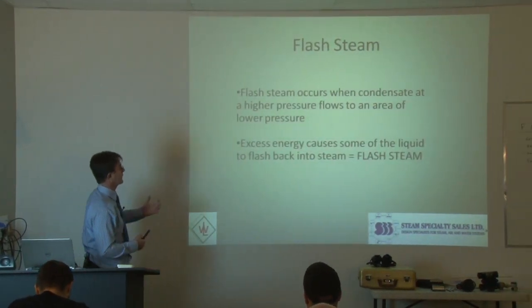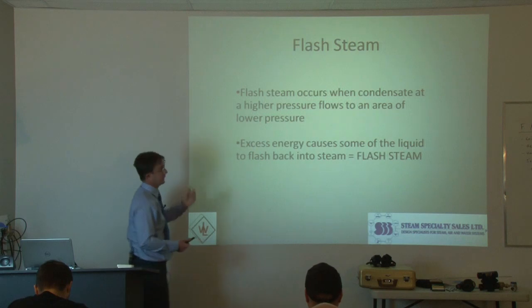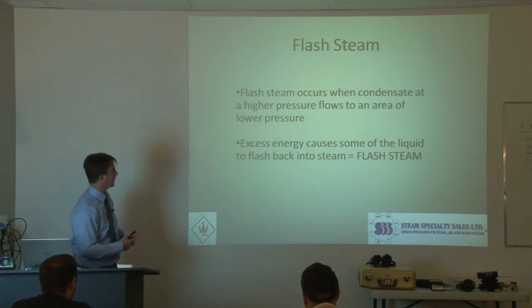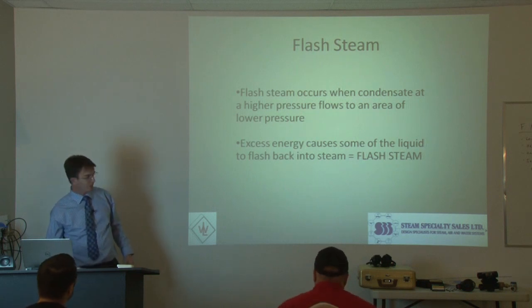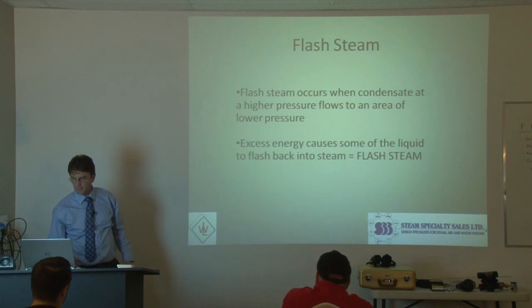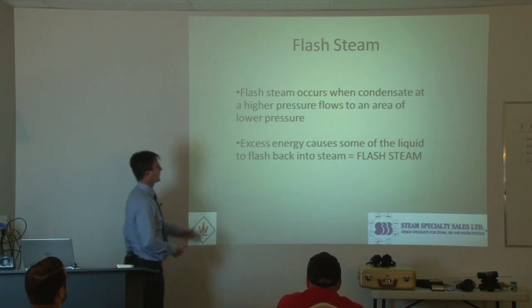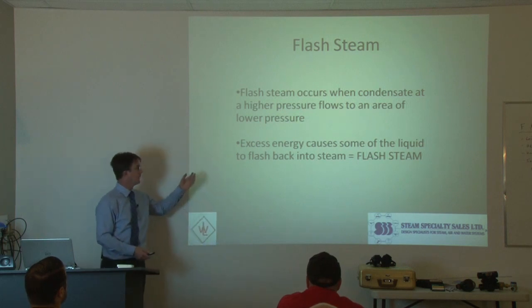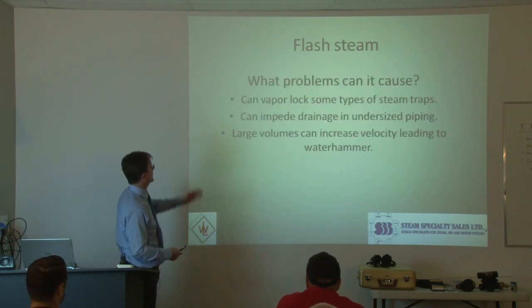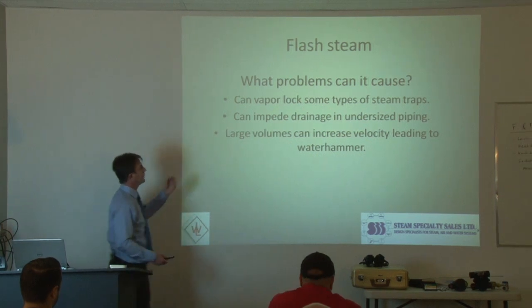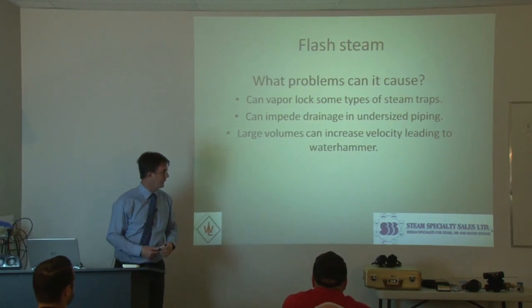Which brings us to the topic of flash steam. Flash steam is one of those tricky concepts that some people understand and others don't. Flash steam occurs when condensate at higher pressure flows to an area of lower pressure — excess energy causes some of the liquid to flash back into steam. It can cause vapor lock in some types of traps, can impair drainage in undersized piping, and large volumes can increase velocity leading to water hammer.